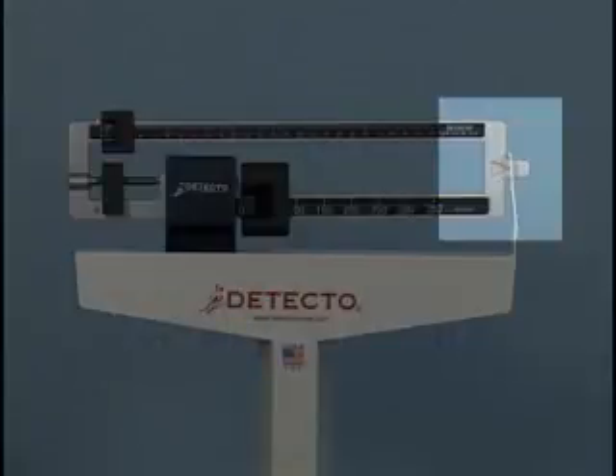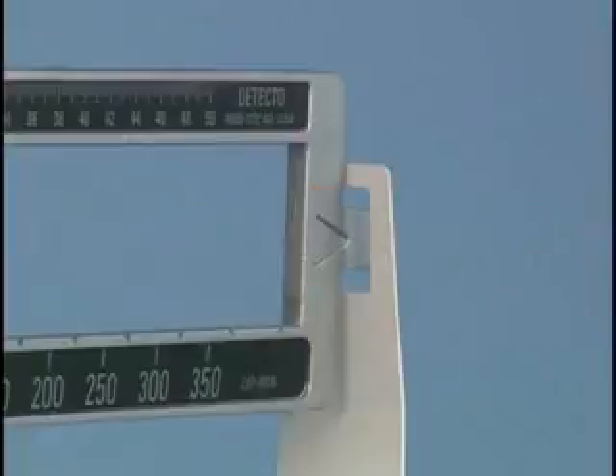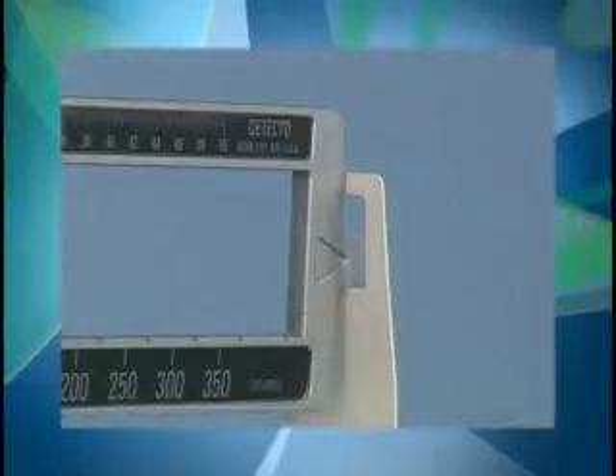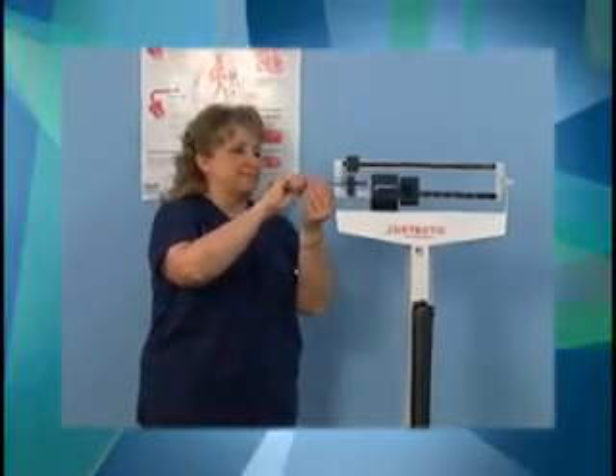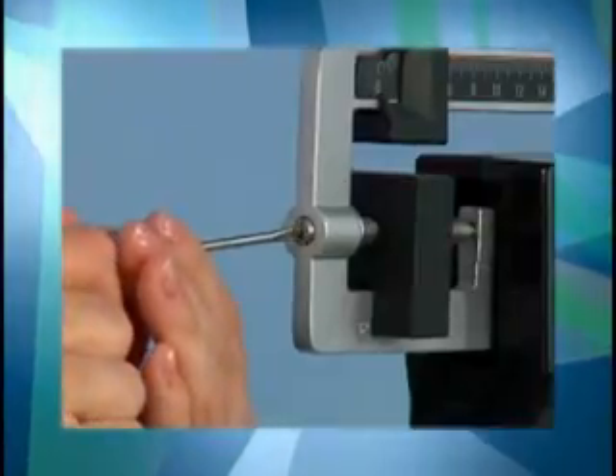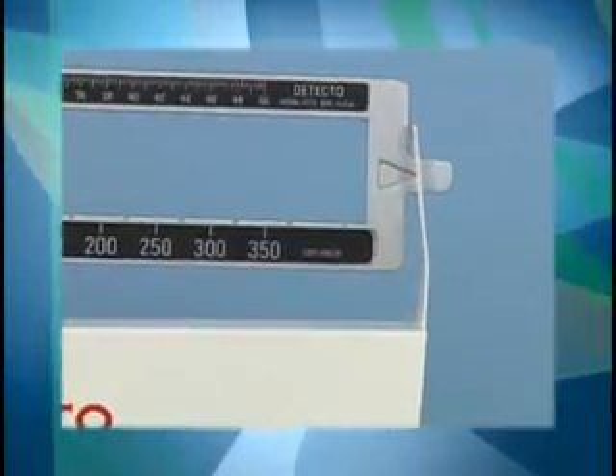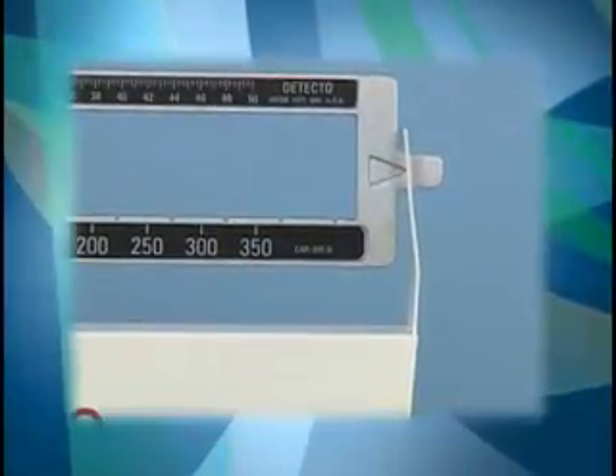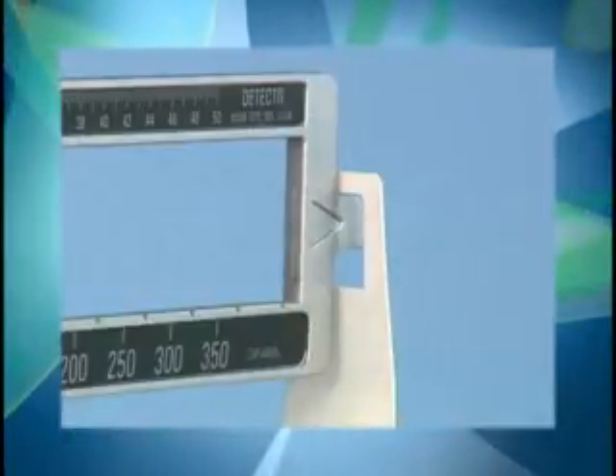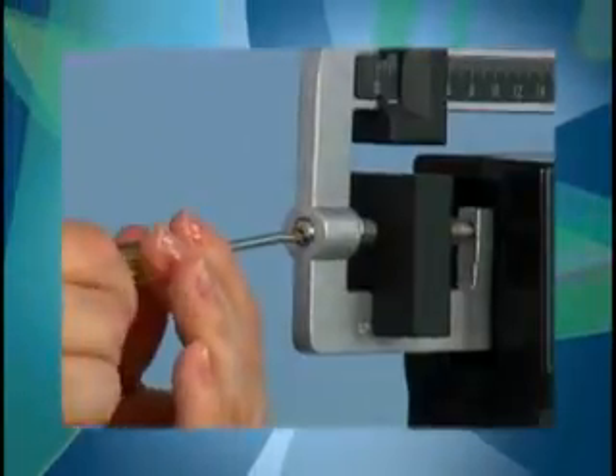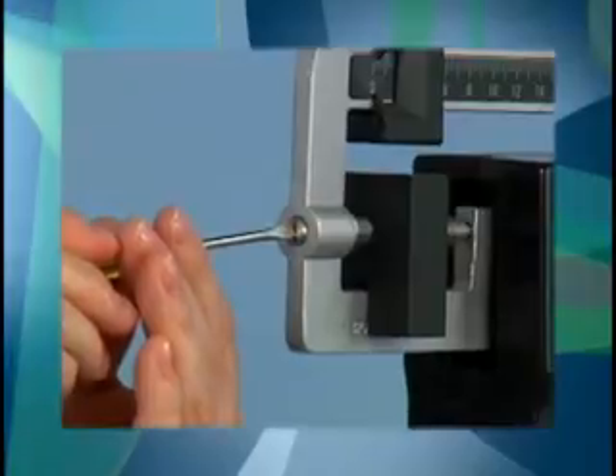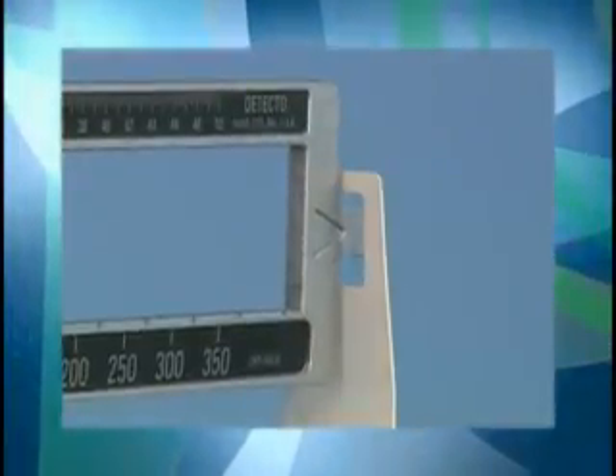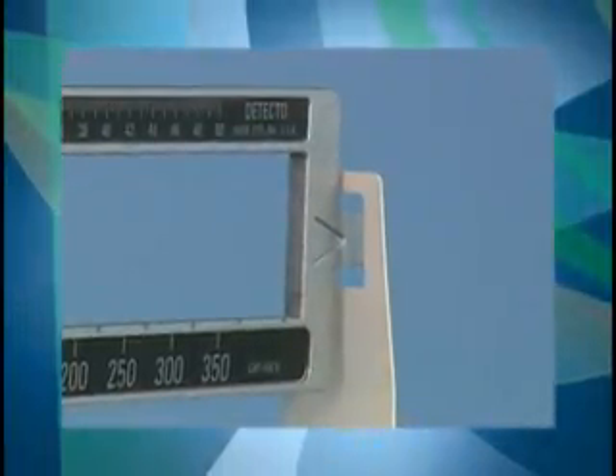Look at the indicator point. It should be resting in the center of the balance area. If the indicator point rests below the center, adjust the screw on the balance knob by turning it clockwise or to the right until the indicator point rests in the center of the balance area. If the indicator point rests above the center, adjust the screw on the balance knob by turning it counterclockwise or to the left until the indicator point rests in the center of the balance area.